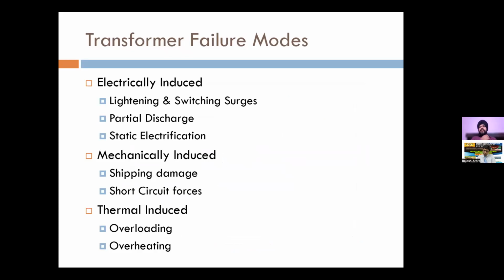Now, if we talk in detail about transformer failure modes, transformer failure modes can be electrically induced, like lightning and switching surges. Then it can be partial discharge, static electrification, or mechanically induced damage, which means that there is some mechanical failure mode, which can be due to improper transportation. If it has been transported and the transformer has experienced some jerks, or during service, if there are frequent short circuits in the downstream network, then the transformer will experience short circuit forces, which would in turn cause damage to its winding, because electromagnetic forces will be generated and windings will also shift. So this is a mechanical failure mode.